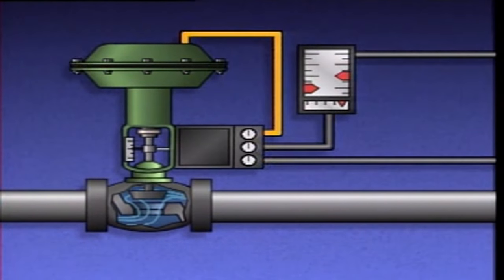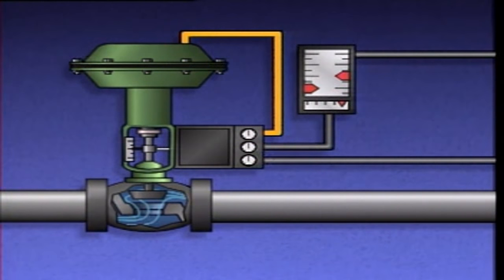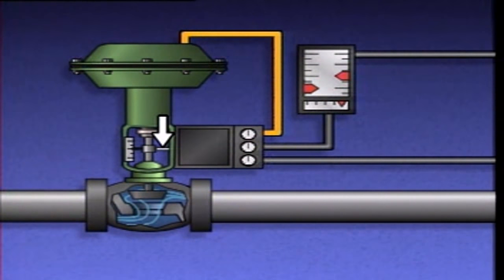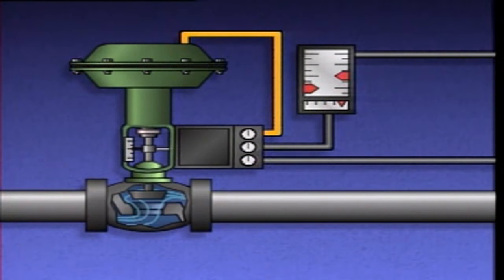This pressure is then applied to the actuator to close the valve. The feedback linkage indicates to the positioner how far the valve is from the desired position — in this case, fully closed. As the valve moves toward the fully closed position, the feedback linkage causes the positioner to change the air signal to the actuator.